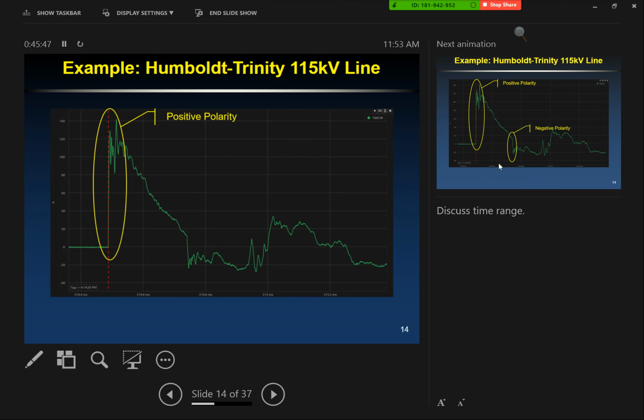This is 140 amps to 0 amps, so you get a pretty good spike. This is an actual fault event. The fault hits the line, and after some time delay, you capture it at the location of the relay. That's this first big jump, and we notice it's positive polarity.